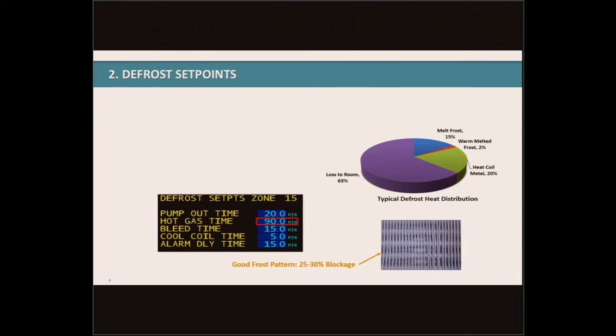Moving over to defrost set points, evaporator defrost is another opportunity to save energy, primarily because defrost introduces a heat load into the refrigerated room. So where does this heat come from? If you look at the pie chart here, when an evaporator goes into defrost, and this is specific to hot gas defrost, but you can really use the same concepts for other types of defrost, like electric defrost. But in the blue slice of the pie there, you can see the energy from the defrost to actually melt the frost in the coil only constitutes about 15% of the energy that's used in the defrost cycle. The big slice of the pie there, the loss to the room, is 63%. So 63% of our heat energy is actually going to losses in the room, which doesn't make for a very efficient cycle. Unfortunately, that's what we're stuck with because we do need to have defrost on our evaporators.